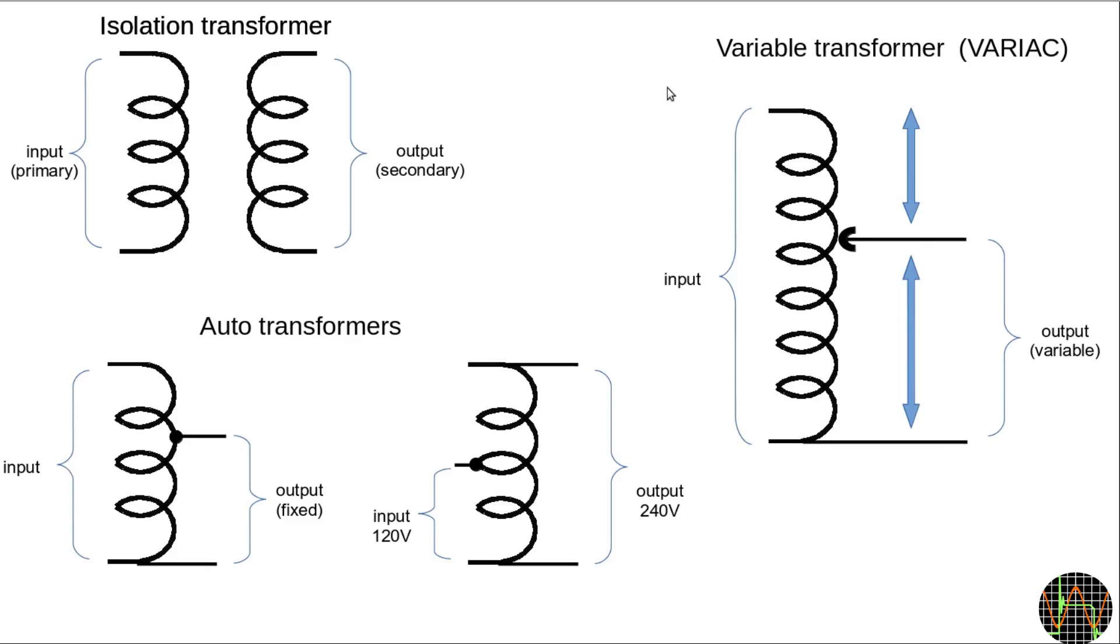The variable transformer solves that by providing an unlimited number of taps and therefore freely selectable AC output voltage, hence VARIAC. It is a special kind of autotransformer using a slider arrangement that connects the output to any position of the coil, a bit like a potentiometer for resistance.